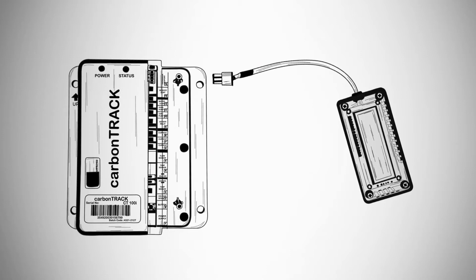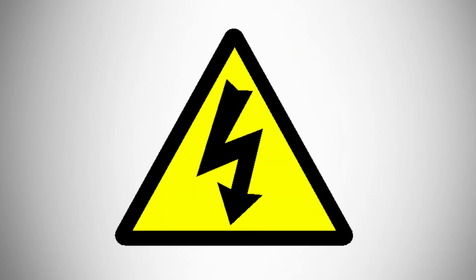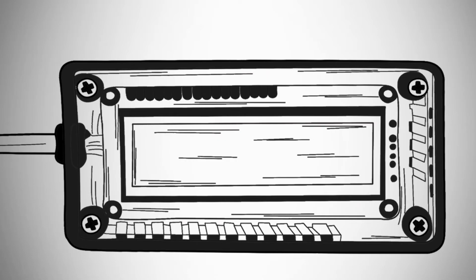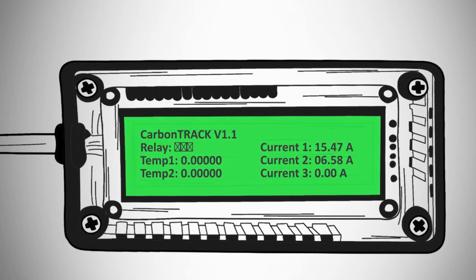As an installer, you will have a handheld tester connected to port number 13. You will see all the parameters sensed by the unit come up on the screen. At this point, you need to ensure that the main switch and the inverter switch are on. 6 parameters will be displayed on the handheld tester screen. 4 of them, relay, temperature 1, temperature 2, and current 3, are not relevant to this installation.